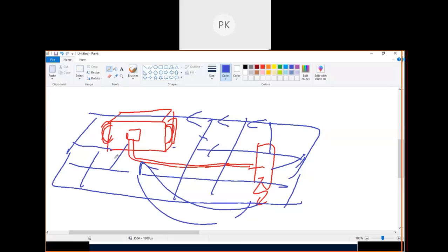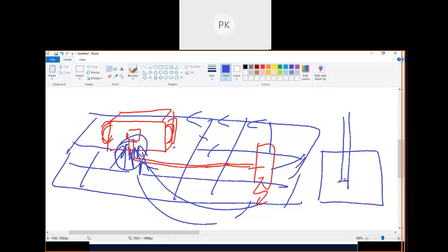But finally, all those currents will come together at this point, and that is the place where the neutral is. At the neutral, since the currents get together, the current is high, whereas at other places it is distributed. That is the reason I want a large area, and hence I am using plate earthing for the transformer neutral. Since my current is more here, the heat produced will be more in the soil. And what happens when the soil heat is more? Can anybody tell what happens?